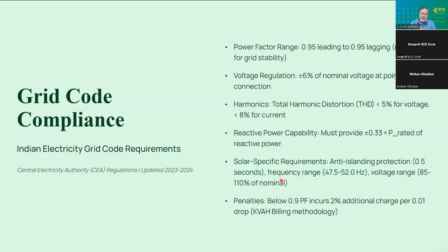Now, since we are talking specifically about solar, the anti-islanding protection has to work in half a second. As soon as the grid codes are not met, whether the frequency is out of range or the voltage is out of range, the solar inverter has to trip within half a second. That's what we are targeting as per the CEA, Central Electricity Authority, grid codes.